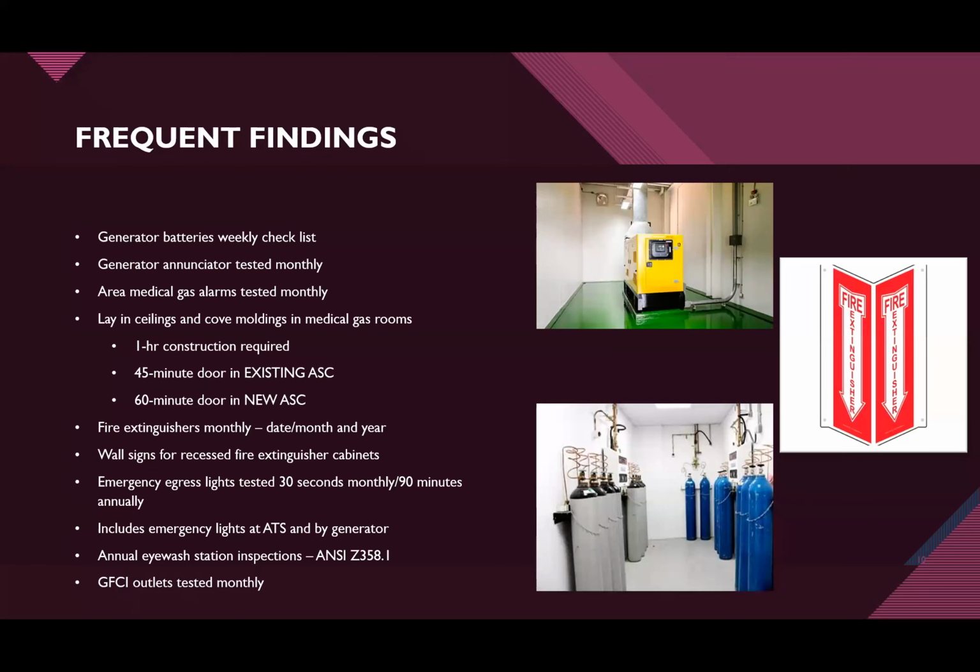And so if you have a duplex system, meaning you have those big H tanks that are in some room, and you've got 3 or 4 on one side and 3 or 4 on the other side, that's a type 1 system, and they have area alarms, and you need a minimum of 2. And the newer ones have a push to test button, and a new log just came out for your review if you are doing that. So you just push the medical gas alarm test button monthly, and you should have visual and audible alarms that say that your panel is working.